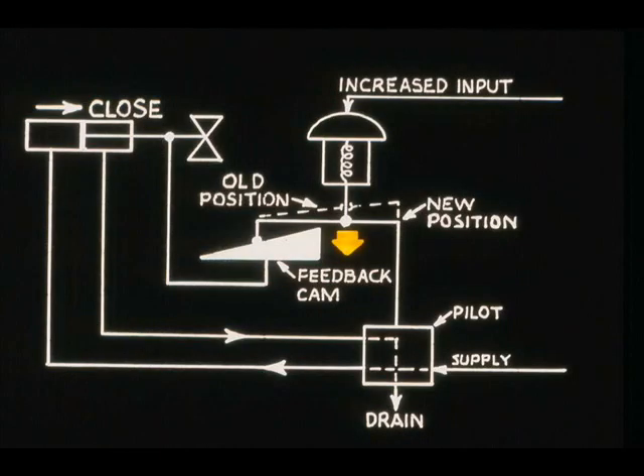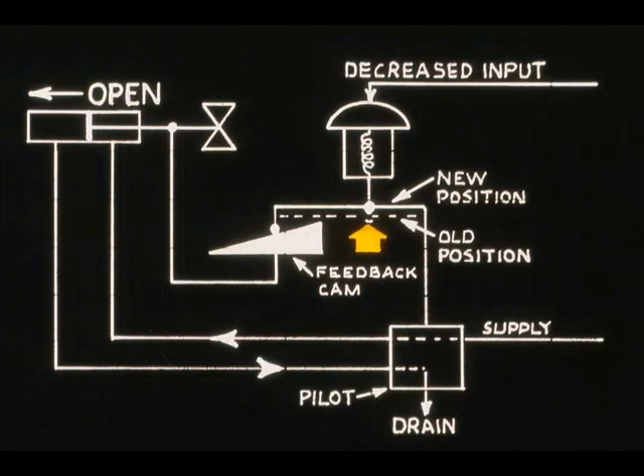So by increasing the input signal, we move the pilot and close the valve. By decreasing the input signal, the pilot reverses the ports and opens the valve.